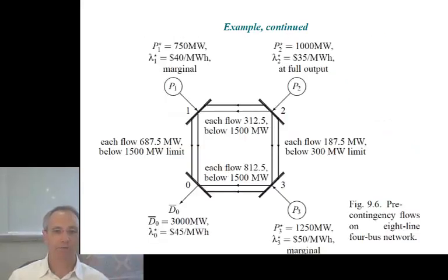So in particular, if we consider our dispatch to be secure with respect to the contingency of either one of the 2 lines on the 2 to 3 corridor, we would find that the actual flows on the lines pre-contingency, in the typical event that the contingency isn't occurring, is rather different, and generally speaking, on the binding limit, lower than the flow calculated for the post-contingency case.